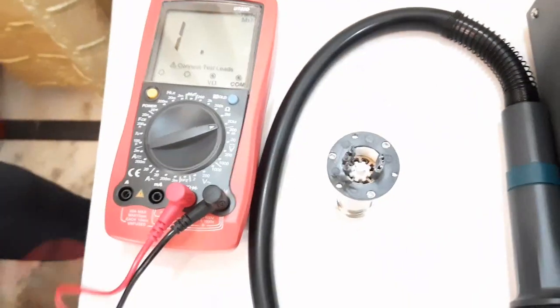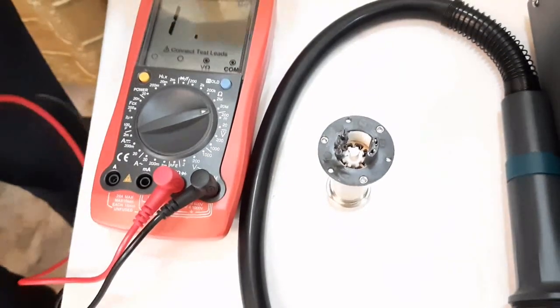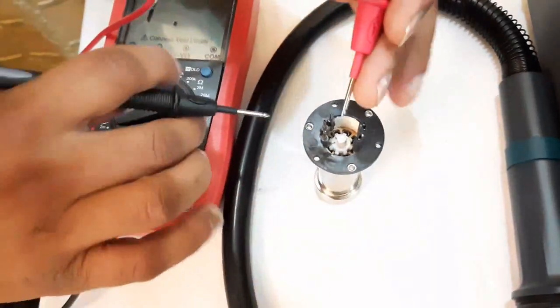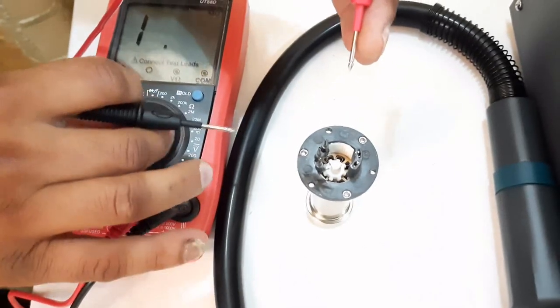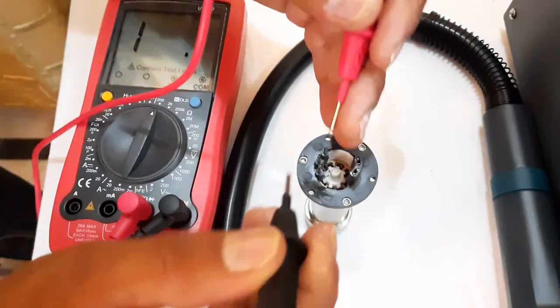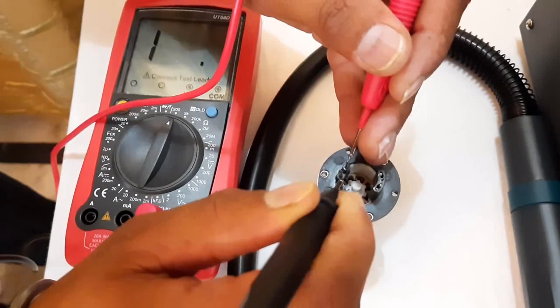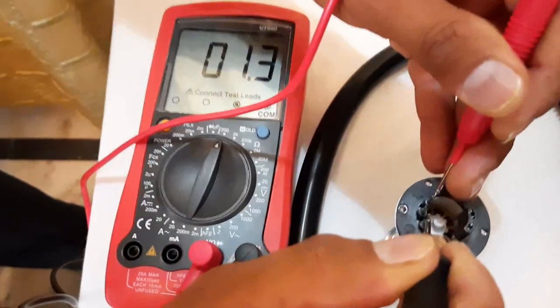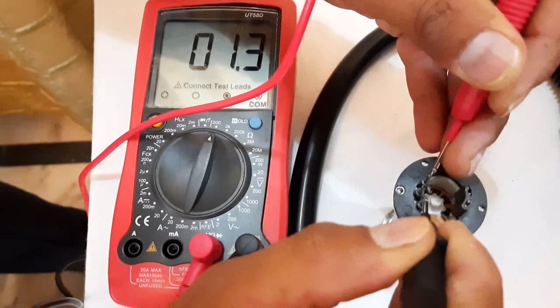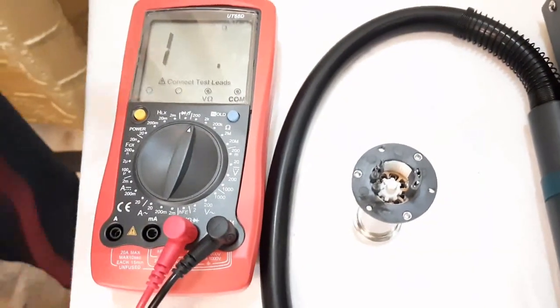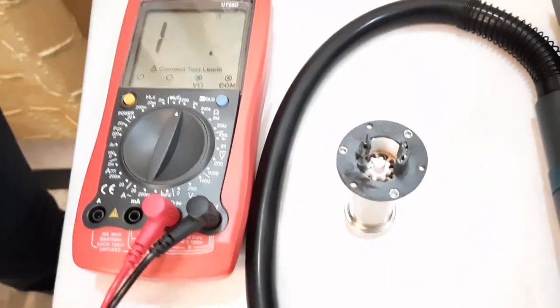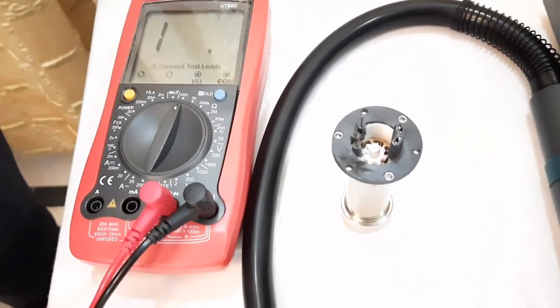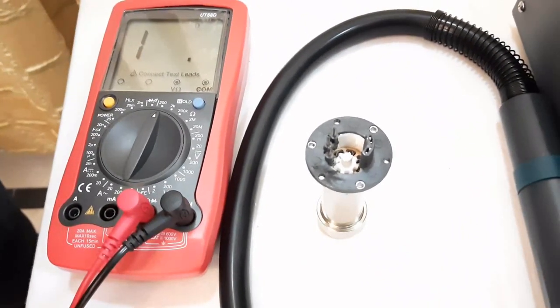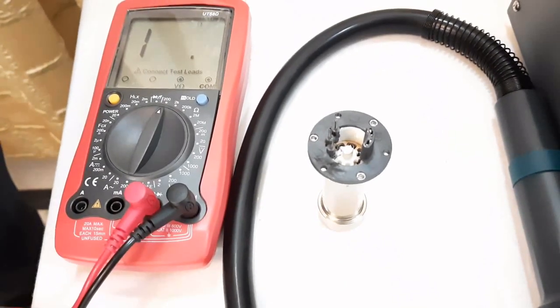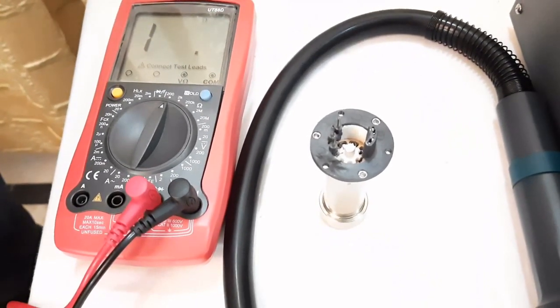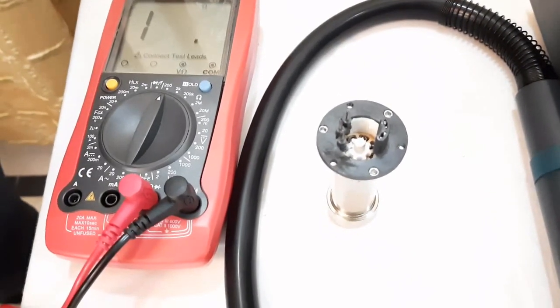Similarly, we can measure the resistance of the heating element as well. It should be less than 2 ohm or 3 ohm. We can see it is less than 2 ohm. It means the heating element is okay, but the sensor is faulty. In case you find the resistance of the heating element more than 2 or 3 ohm, then you might need to replace the heating element as well. But since both the heating element and sensor are integrated, we need to replace the whole heating element enclosure with a new one.